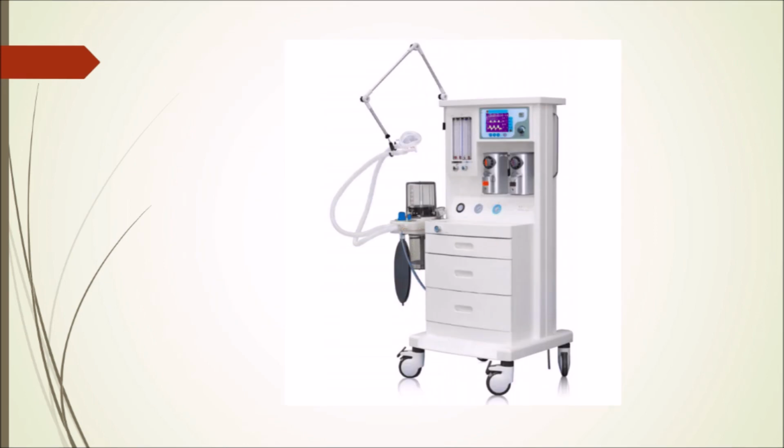Also, the anesthesia machine has a ventilator. The automatic ventilator is generally used to mechanically deliver breaths to the patient. These ventilators use a bellows or piston instead of a manually compressed reservoir bag. The ventilator forces the mixture of anesthesia gases into the breathing circuit and lungs of the patient, and in a circle breathing system receives exhaled gas from the patient as well as fresh gas.